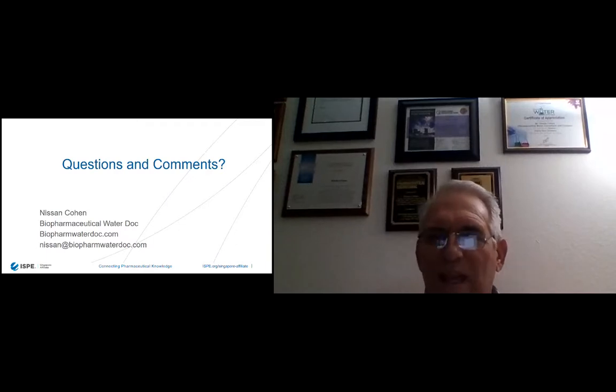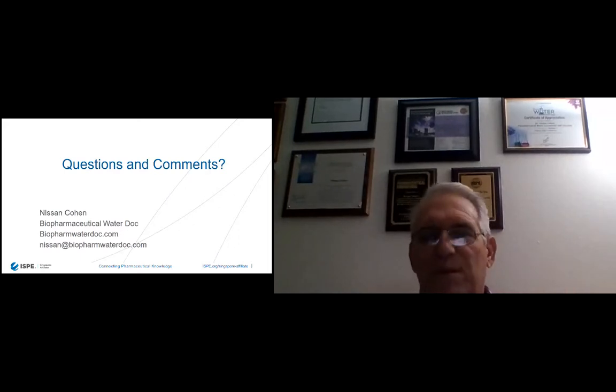The best way to put in a rouge monitor, an online rouge monitor, is directly after you do a derouging passivation or while you do a derouging passivation. So before you do a derouging passivation, install your derouging passivation sensor, or directly after you do the derouging passivation, put in your sensor, having it start with a pristine system at 0 and let it accumulate as the system matures.